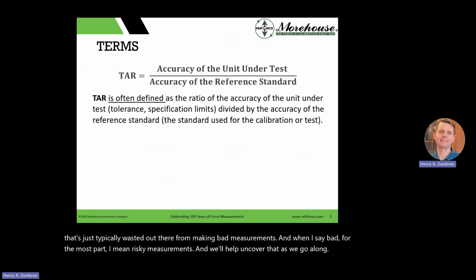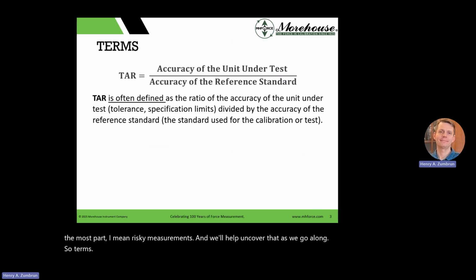So, terms. I always love acronyms, right? Everybody speaks them and then they never define them, so we're going to redefine them here. TAR, which is test accuracy ratio, is typically referred to as the accuracy of the unit under test to the accuracy of the reference standard. That's it. We have the tolerance specification limits divided by the accuracy of the reference standard.